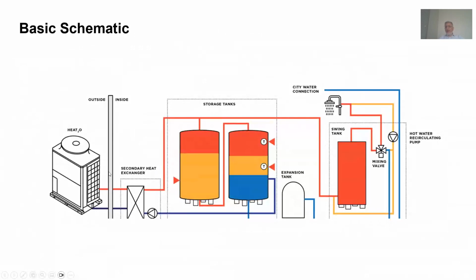A typical application, again, coming back: you have a hot water generator or a CO2 heat pump that provides hot water through a heat exchanger to the tanks. You have sensors depending on what temperature you set there. But in the beginning we have seen that these machines were designed for a high delta T application. So if we try to recirculate this hot water back to the cycle, it will decrease the efficiency of the system. So it's not recommended to use hot water going back for recirculation.